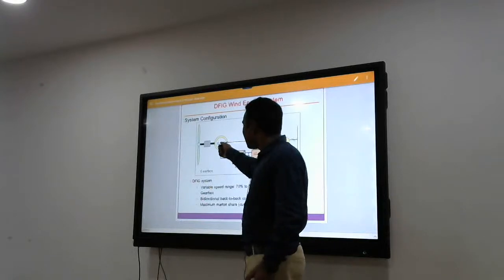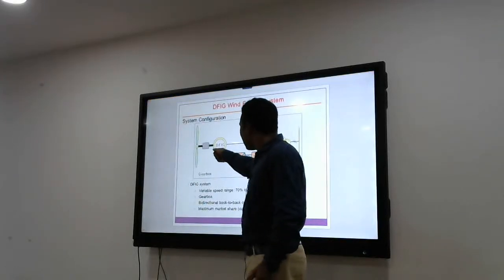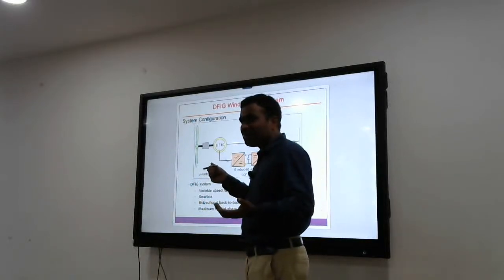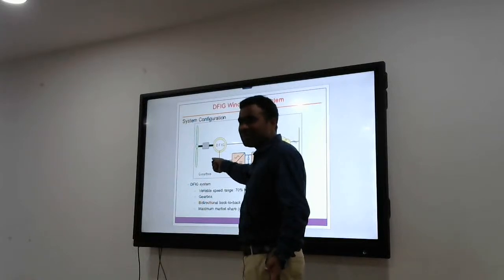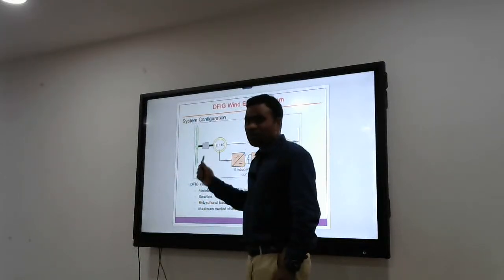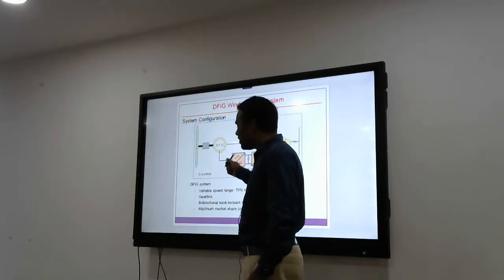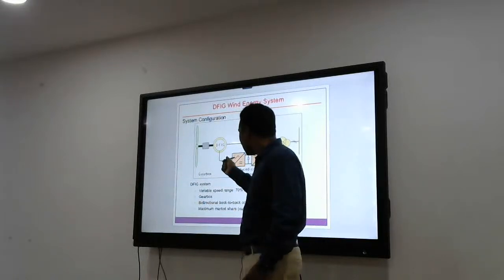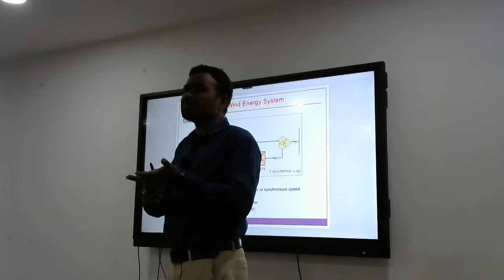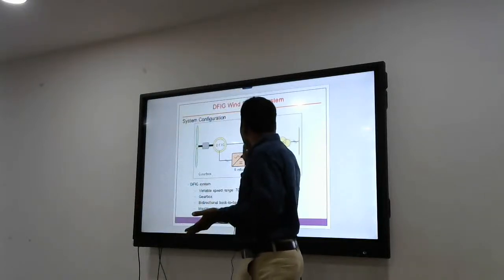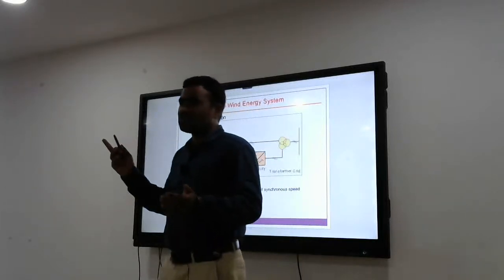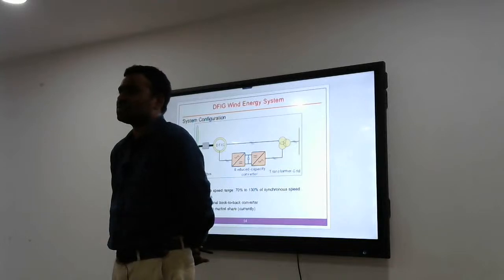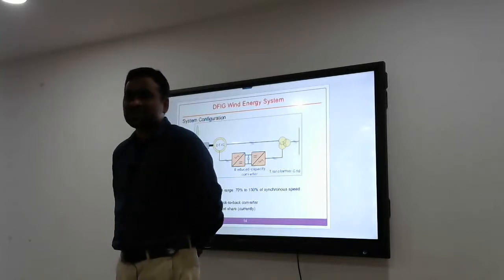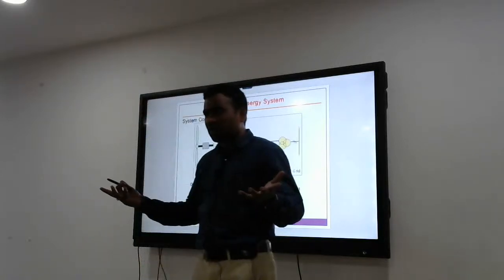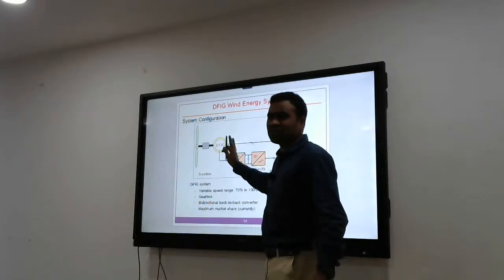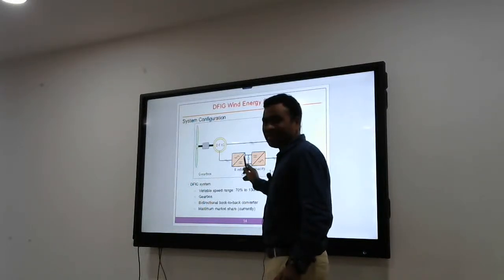Suppose the stator voltage is 11 kV, then the rotor voltage will be 11 kV into 0.3. Here the required is 3.3 kV. So these converters need to handle very low voltages as compared to the previous topology. The voltage requirement is less, and the power requirement is less. That's why this is the topology that people are mostly using for wind energy conversion systems. Around 50% of the installed wind turbines all over the world are of this DFIG nature only till now, because the converter rating is very less.